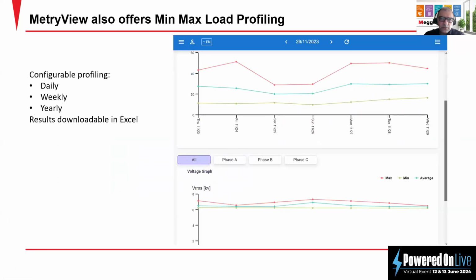Min and max load profiling. This can be configurable daily, weekly, and yearly, and can be downloaded in Excel files. In some areas, like rural areas or old substations, they don't have any monitoring system, and they want to do some investment planning or changing. They're using this profile to make a decision on which part of the network needs to be replaced.